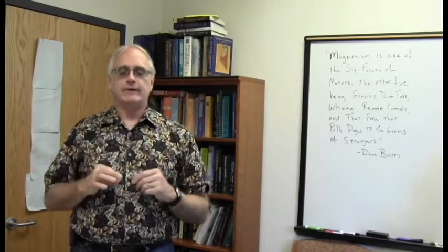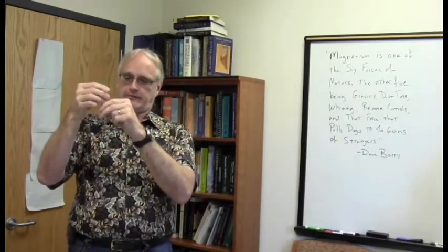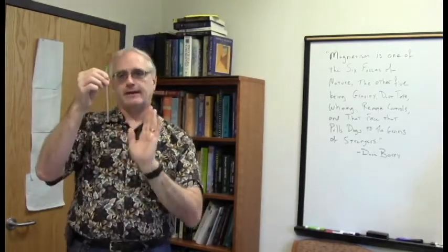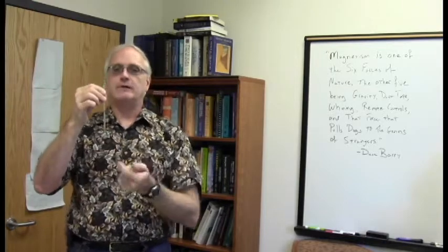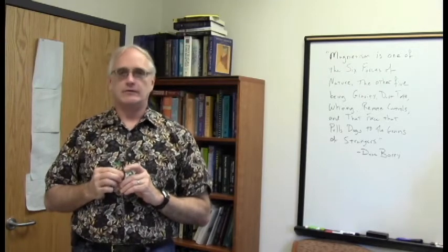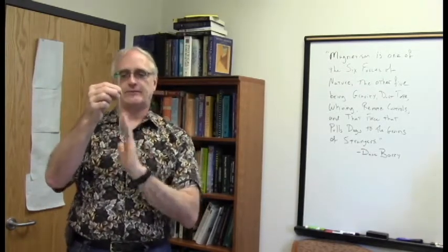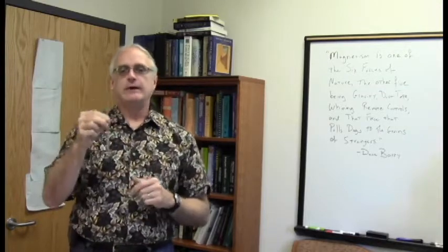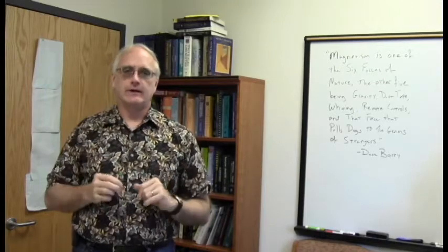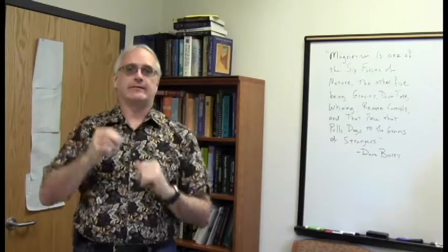One way of doing that is to spin the sample on its long axis, rotating at around 20 revolutions per second on our instrument. The idea is it makes the front, back, left, and right rapidly trade places, averaging out any differences in those directions. The real work comes along the long axis — making sure the magnetic field is homogeneous along what we refer to as the z-axis.